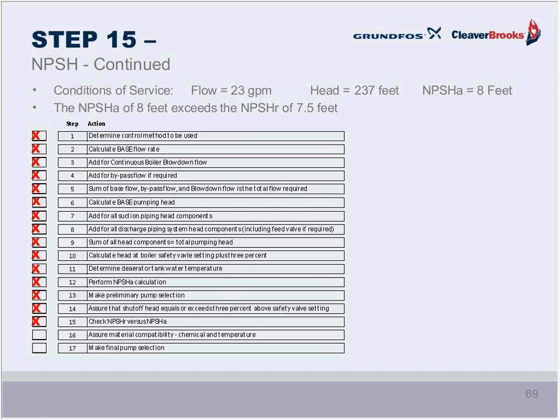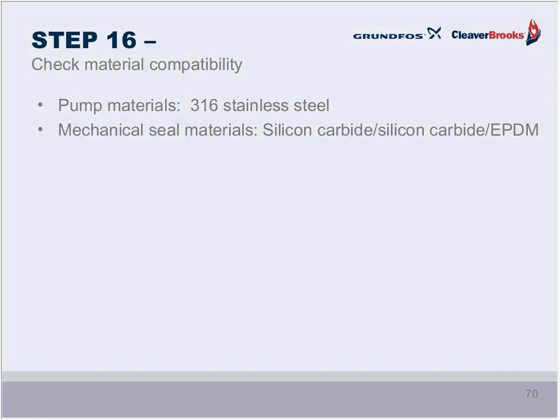Just a couple more steps here. We have to check material compatibility according to that process checklist. We were specified with 316 stainless pump materials and the mechanical seal materials, as you can see here. And the pump manufacturer confirms that, yes, that pump is available in those materials, so it meets the specification.